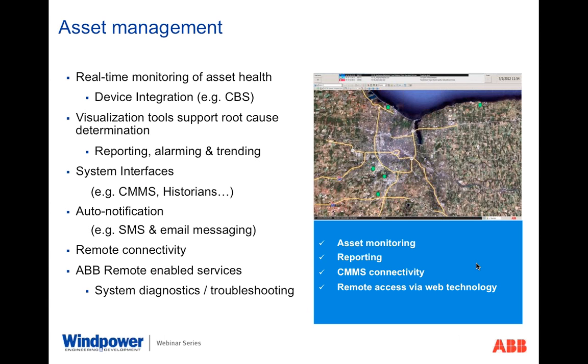Our asset optimization system provides complete integration of devices regardless of manufacturer or type. Features such as asset condition monitoring and reporting ensure fast, reliable, proactive implementation of corrective measures. Intelligence of the cause and recommended actions support the users to decrease the time to repair, as well as reduce the number of substation visits to identify the problem or even have the adequate tools and parts required. Alarm reporting features can be utilized to support KPIs, the key performance indicators, and long-term trending features provide early indication of the health of the assets.